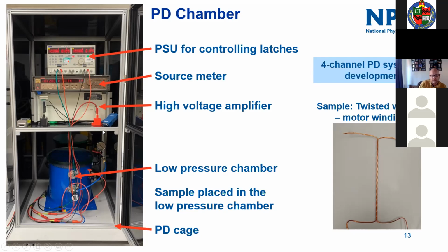And what's not shown here for some reason is the waveform generator. The whole thing, as you can imagine, is inside a very large cage with interlocks on it, and we probably spent more time going through the health and safety assessment of this than we've actually done any work today, but hopefully that will change. I should say that we are developing a 4-channel system as well at the moment, so we're looking to maintain the aging through the amplifier across 4 samples simultaneously, and then periodically switch in the source meter to measure the insulation resistance as we go through the aging process.